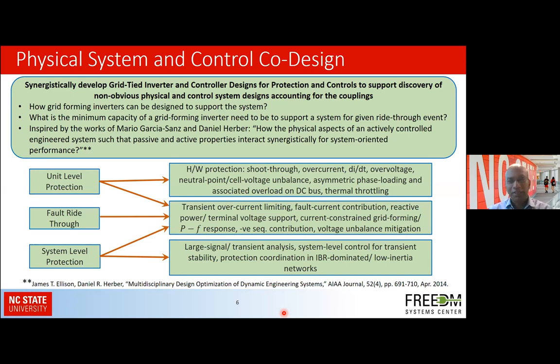So in terms of the faults and protection for grid forming converters, there is a unit of the hardware, the inverter, the IBR, right? So that needs to have its protection at the unit level. Then it interacts with the system, and then there is system level protection also. So for the unit level, it needs hardware protection, the shoot-through protections, the di/dt limits. If an NPC type power converter is used, then cell voltage balancing, and then handling asymmetric phase loading. Those types of protection components have to be incorporated in the controller for the unit. Thermal throttling for device derating, those all have to come.